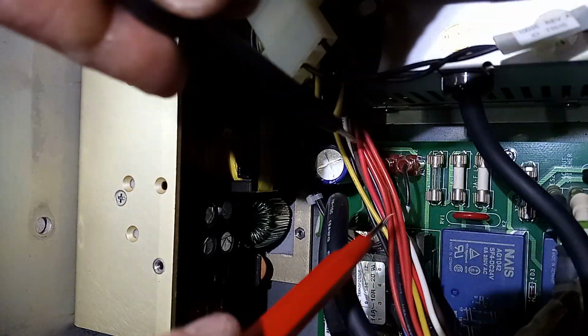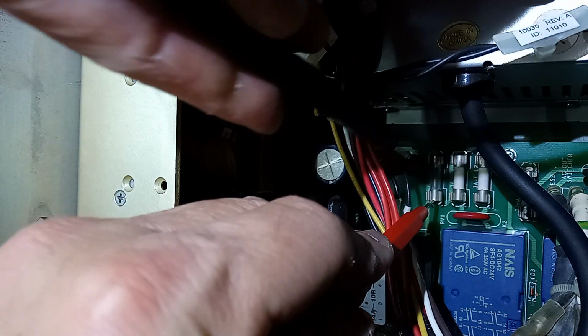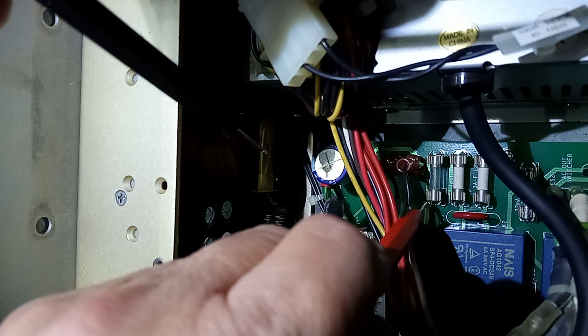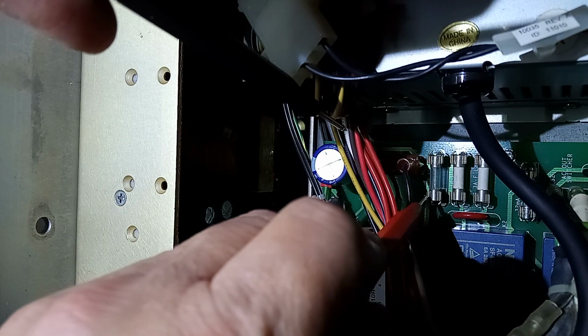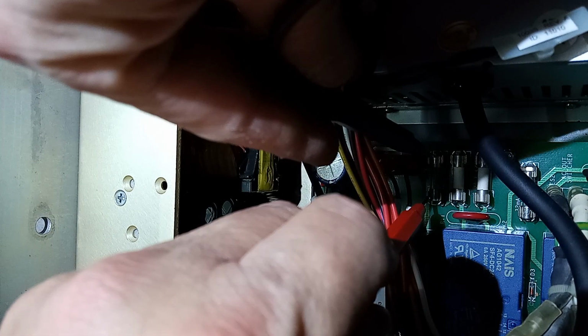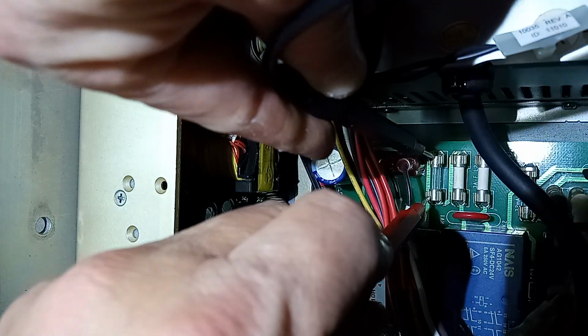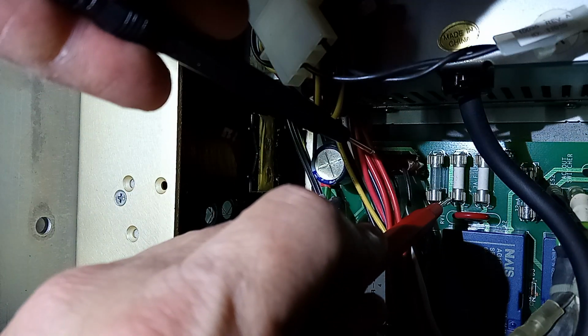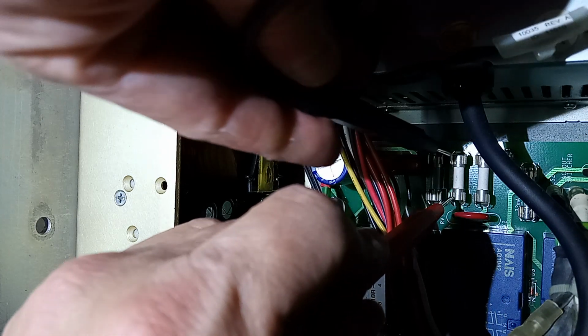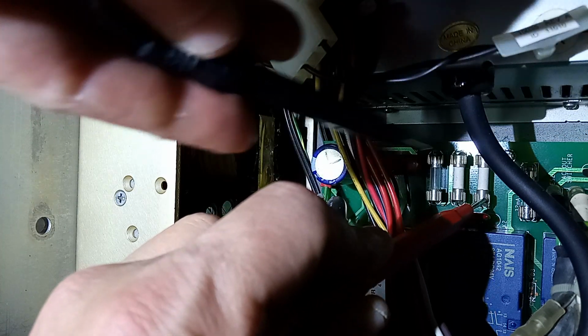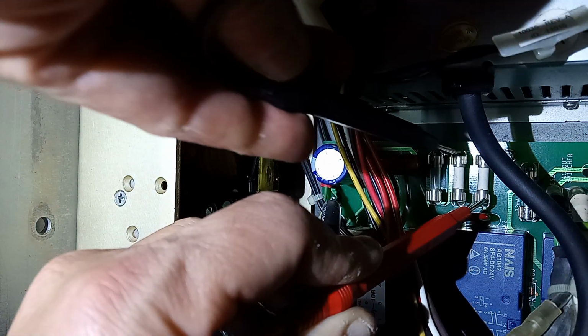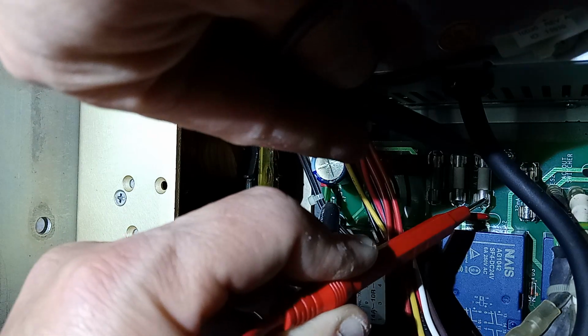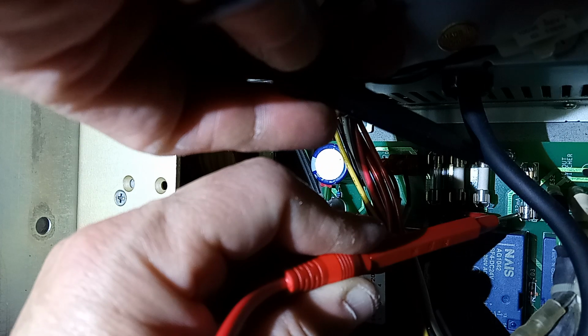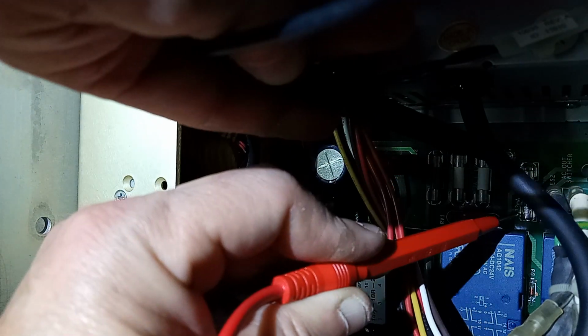So we're going to start probing over here. That's the first fuse, a 100 milliamp fuse, the first one in line. That one's giving me a beep, so it's good. The second one is 6.3 amps, the one in the middle, and then the one next to that is also 6.3 amps, labeled L2. That's good. Then a 32 milliamp fuse, which is the E-stop fuse.